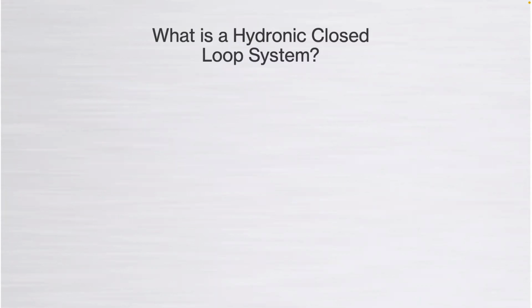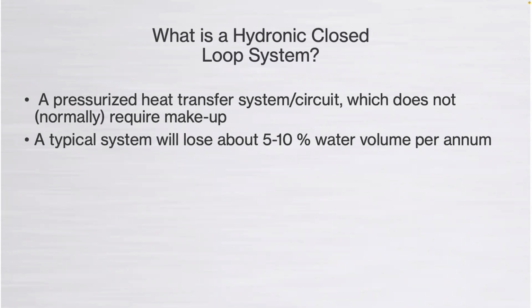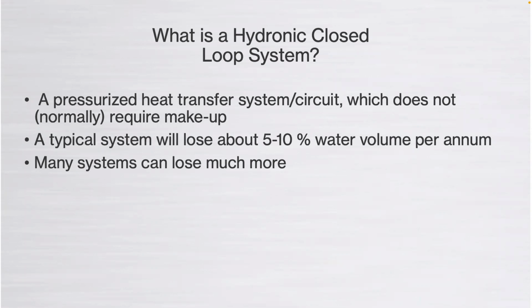So what is a hydronic closed loop system? Essentially, it's a pressurized heat transfer system or circuit, which does not normally require makeup. A typical system, believe it or not, will lose around 5 to 10% of water in a year, which is actually a significant amount. That's because we use various materials and gaskets and so forth that we can't really create a true sealed system. They do make up water. And some systems can lose much more.